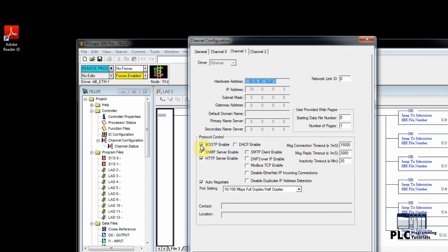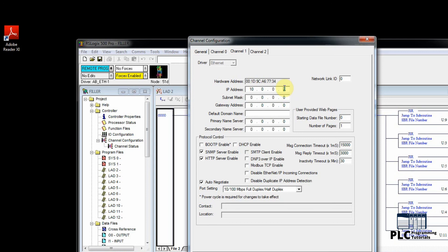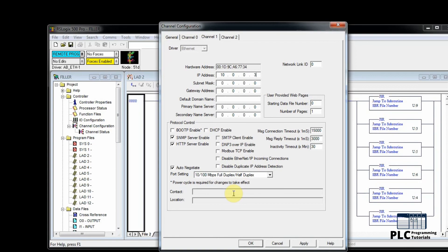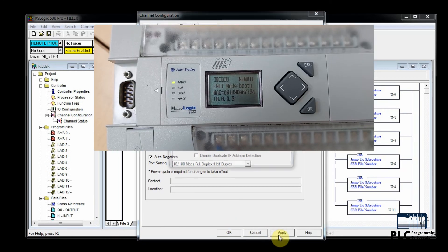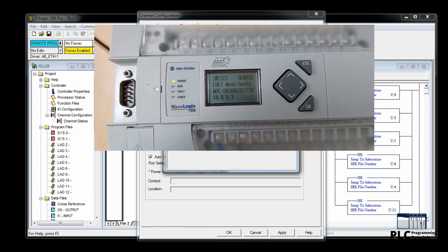Now we will uncheck BootP to disable it, and we can now change the IP address of the PLC. But for now we will keep the same IP address as 10.0.0.3. Now as soon as we click the Apply button, the PLC mode changes from BootP to static.